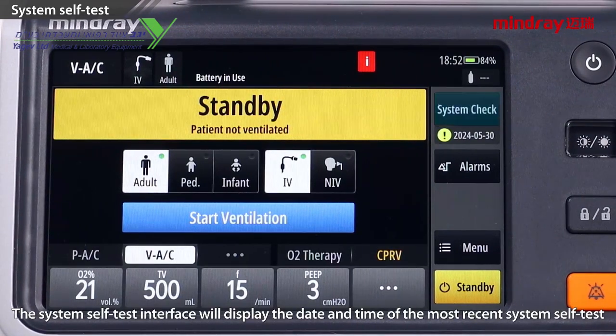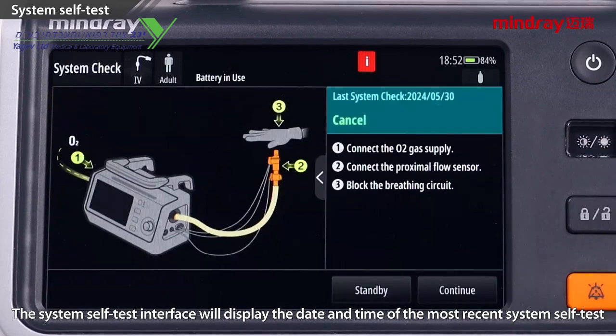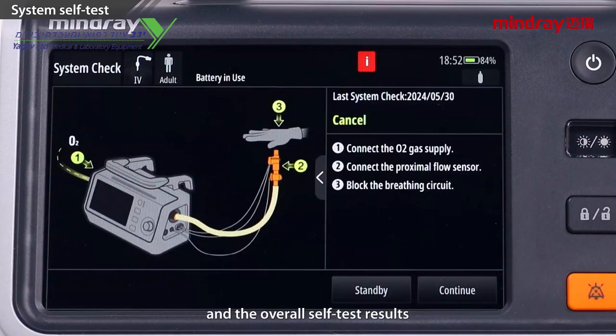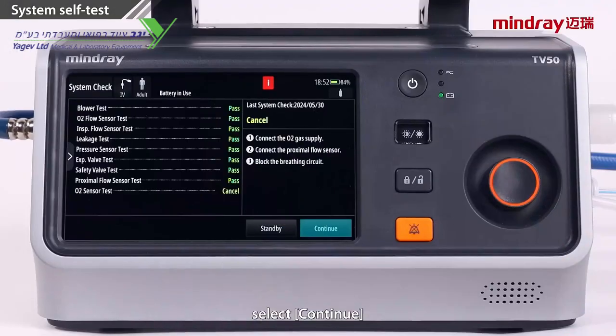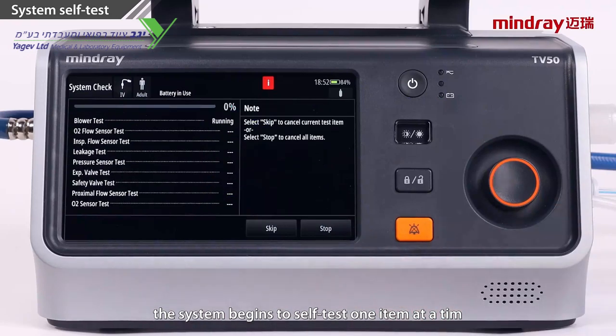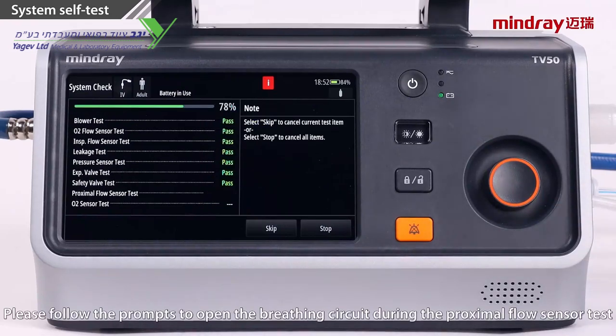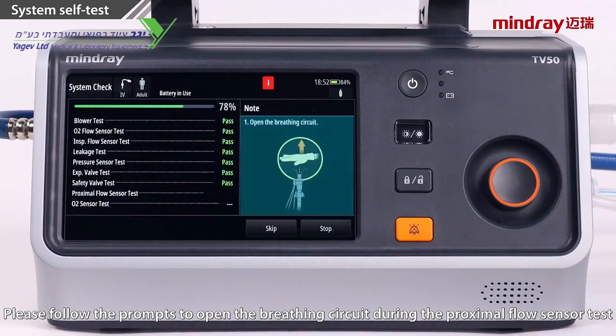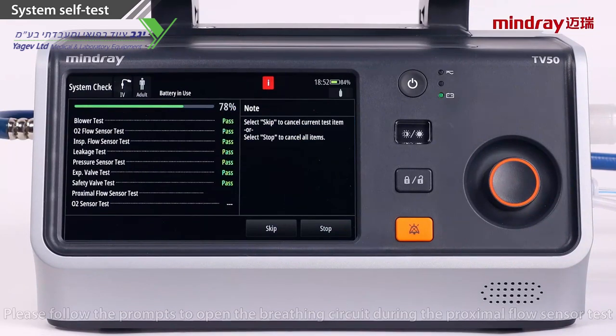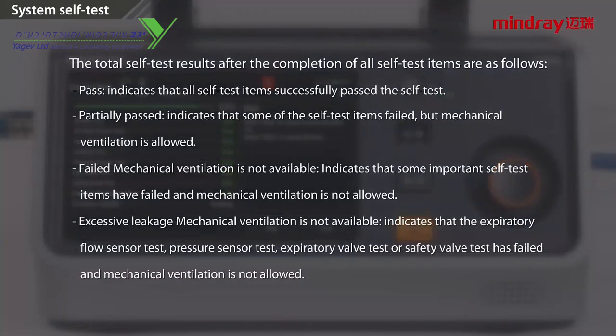The system self-test interface will display the date and time of the most recent system self-test and the overall self-test results. Follow the instructions to connect the air source and proximal flow sensor and close the breathing circuit. After completion, select Continue. The system begins to self-test one item at a time. Please follow the prompts to open the breathing circuit during the proximal flow sensor test. The overall self-test results after the completion of all self-test items are as follows.